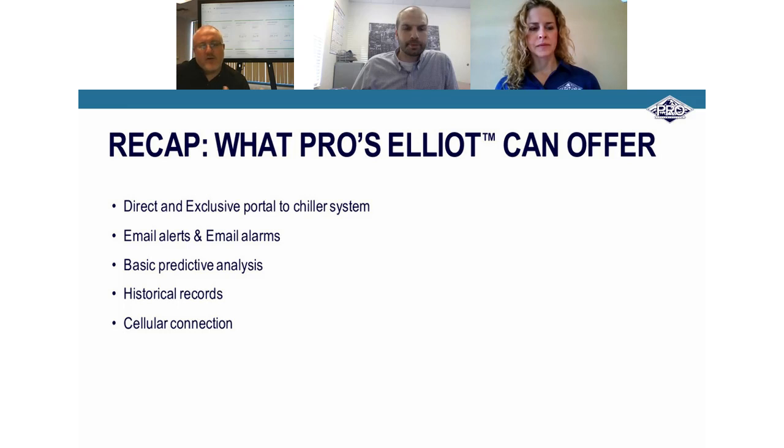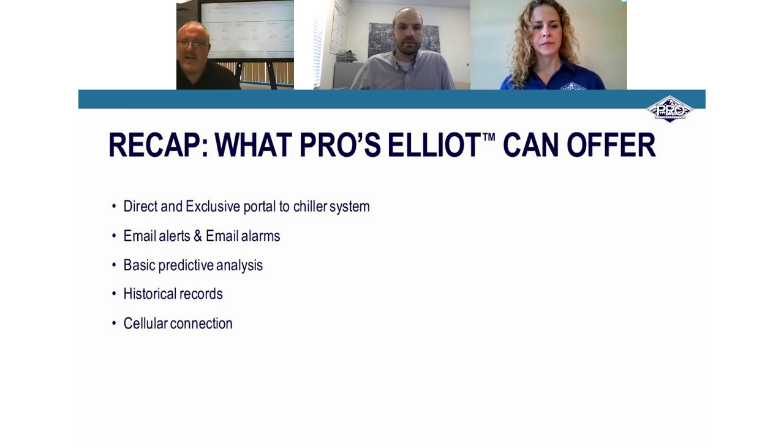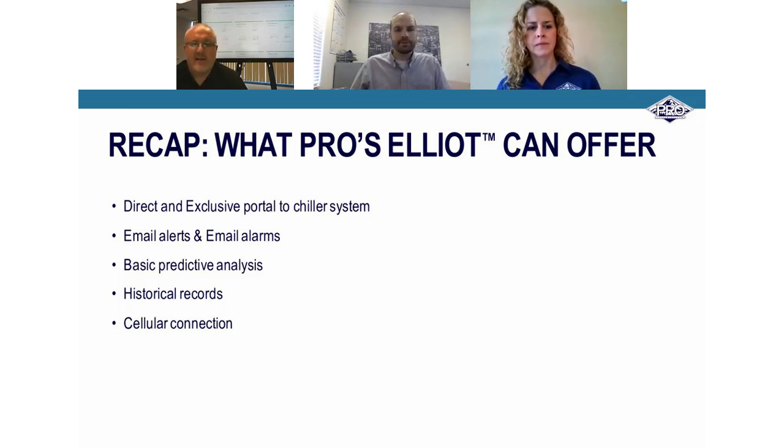So you could go year over year and say, what was my system doing last year? What was it doing the year before? What is it doing this year? Am I starting to see things like, am I having trouble maintaining set point? If everything's operating perfectly, but I'm having trouble maintaining set point, then maybe something changed in my process, and maybe I need a little extra cooling capacity to get myself where I want to be. So having the value of those historical records, I think, is a definite big plus for folks.